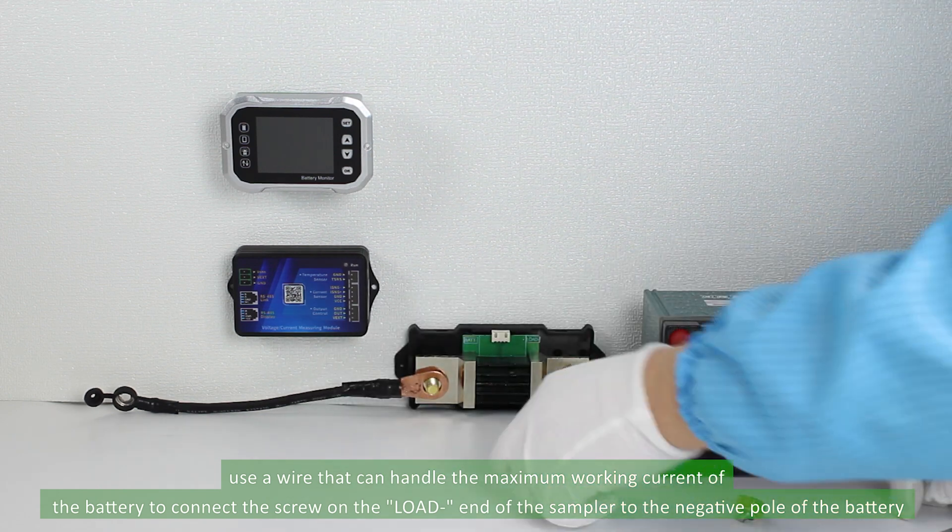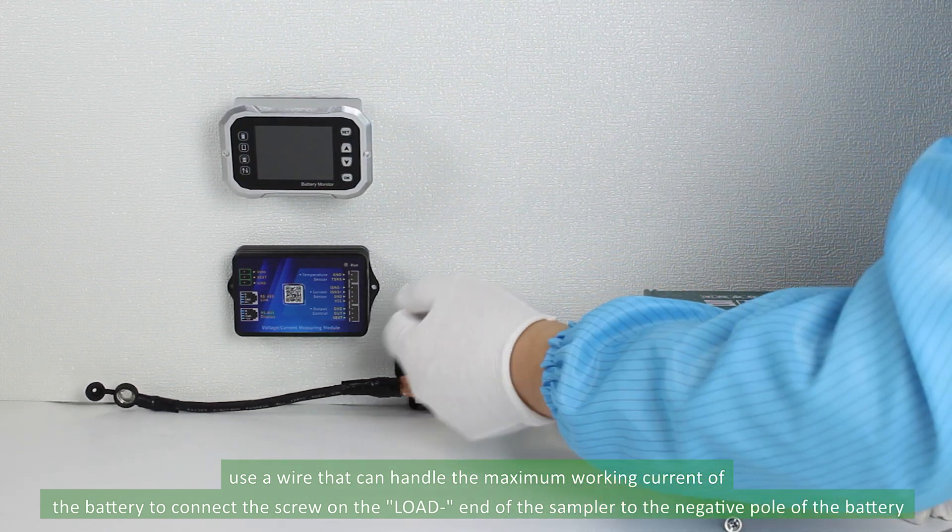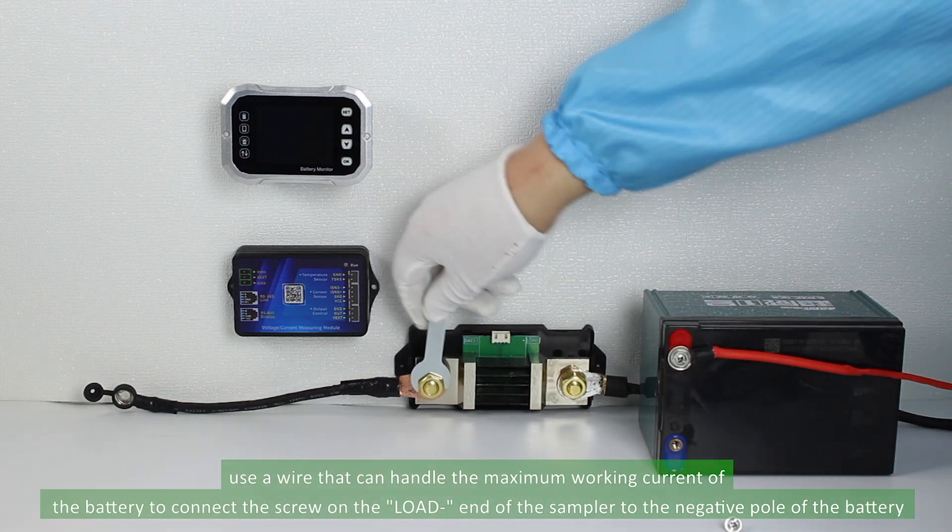Next, use a wire that can handle the maximum working current of the battery to connect the screw on the load end of the sampler to the negative pole of the battery.